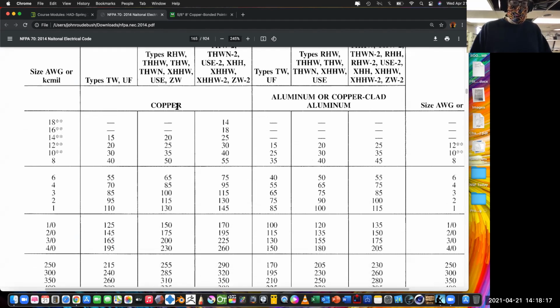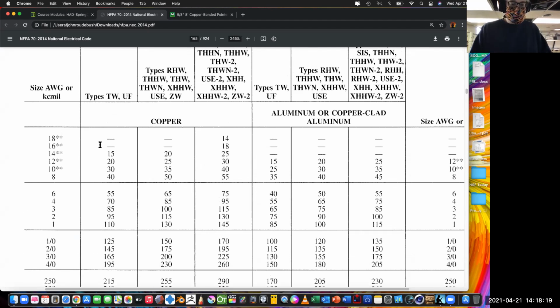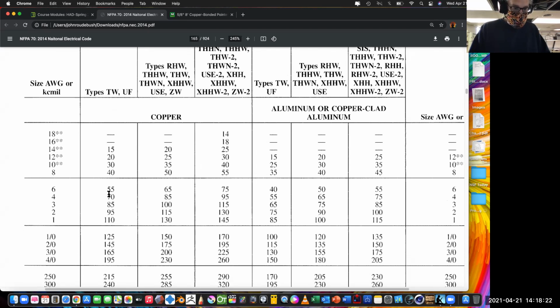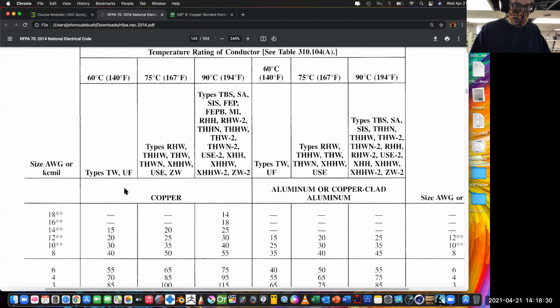This chart is allowable ampacities for insulated conductors rated up to and including 2000 volts. This is for conductors in a raceway, and we're in a raceway because we're running pipe to move our conductors around. We were talking earlier about what we need to do, and we know that we're running up to 60 amps, so we can go down here and look, where is 60 amps? You can run up to 55 amps on number 6.